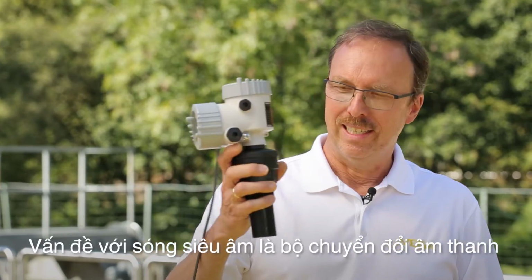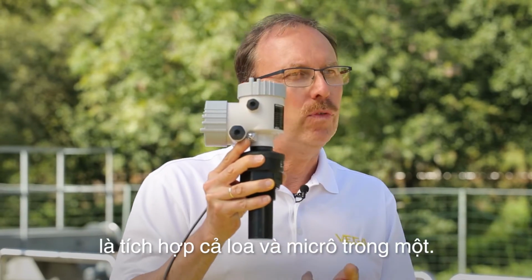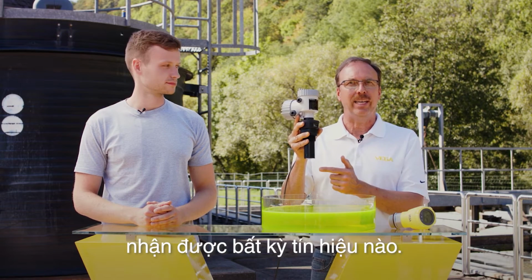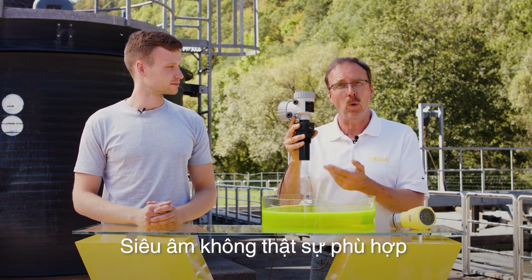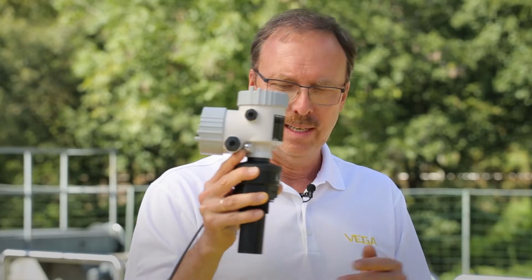The problem with ultrasonics is the sound transducer is a loudspeaker and microphone in one. While transmitting signals, it cannot receive any signals. This creates a blocking distance. Ultrasonic is not necessarily suitable for applications where there's a high chance of overflowing.